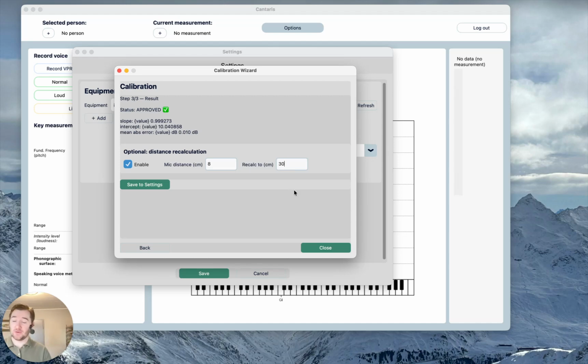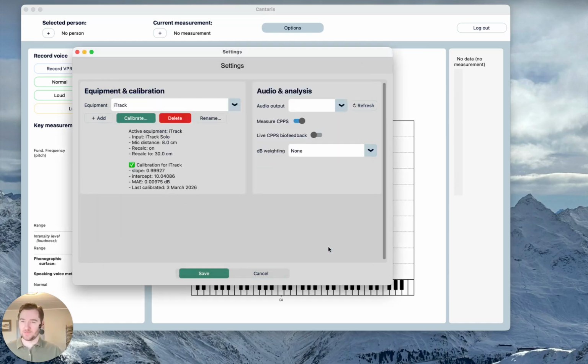Now, what if you're measuring with a microphone at 15 centimeters from the mouth, approximately? Then you might want to enable this, put 15 here and put 30 here. What if you're measuring from 30 centimeters from the mouth? You don't even enable this function at all. Now click Save to Settings and then Close. And right now you can see that this equipment was calibrated today, and in about a year from now Cantaris is going to remind me that I need to calibrate again.